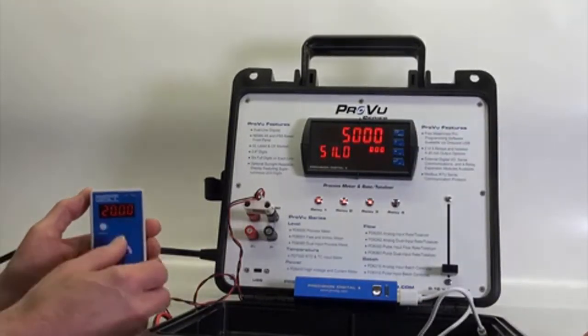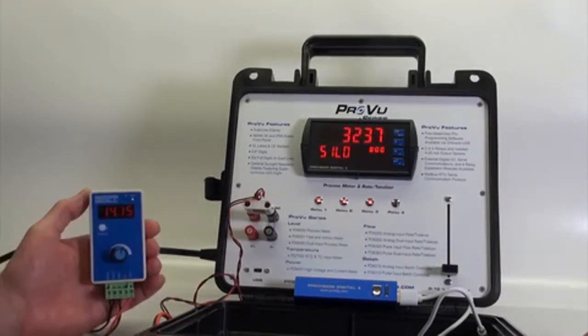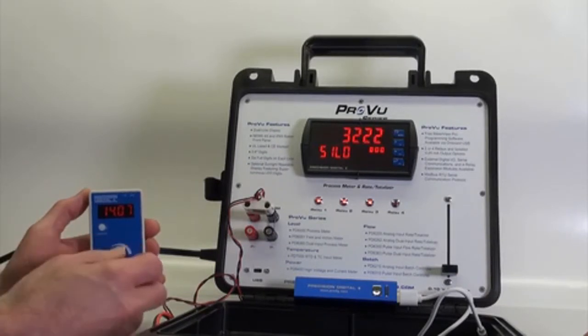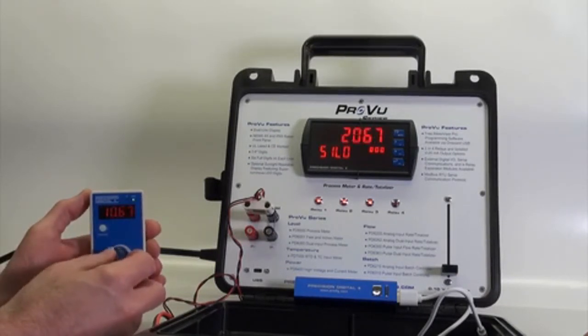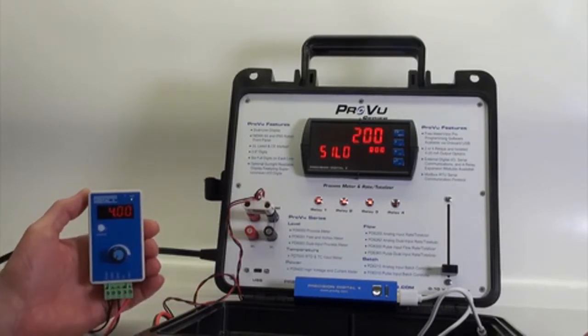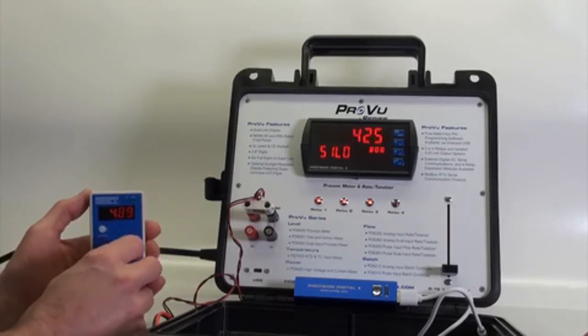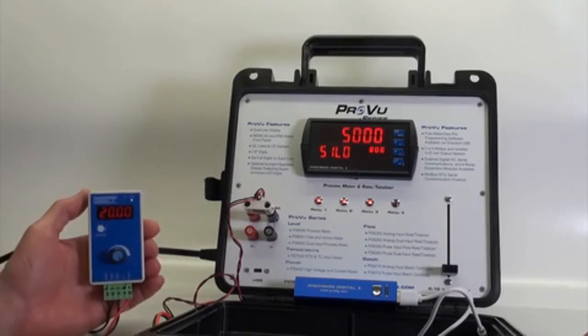And there you go. The PD9502: a simple and easy way to calibrate all of your 4 to 20 milliamp devices. 200 at 4 milliamps, 5,000 at 20 milliamps.